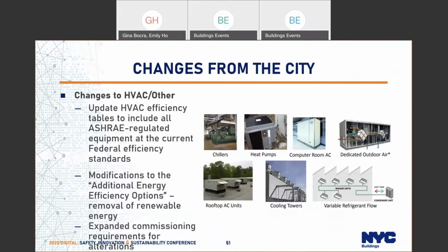There are a few other changes from the city that we would like to make sure you're aware of. There are very minor changes to HVAC efficiency tables all throughout any equipment regulated by ASHRAE. If the federal efficiency standard was higher than the 90.1 table required at the time of publishing, it has been brought up to the current federal efficiency standard within the New York City Energy Conservation Code. So that makes sure that the equipment being installed in New York City is at the highest standard required by the federal government and not lower.